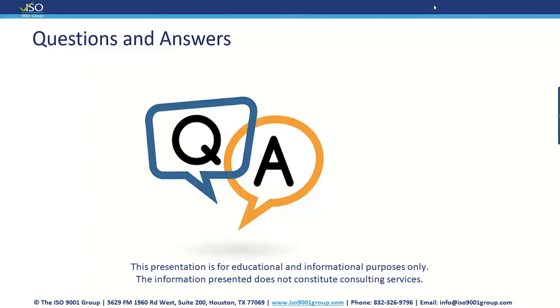Guess what? If the OEM says it needs to be calibrated every 3 years, and you're sending it out every year, you're just literally wasting money. Unless in between that time frame you verified it and it's not reading properly, then you'd want to get it calibrated. All right. But again, just make sure that your standards that you use to verify internally, or at least send out for calibration on an annual basis.